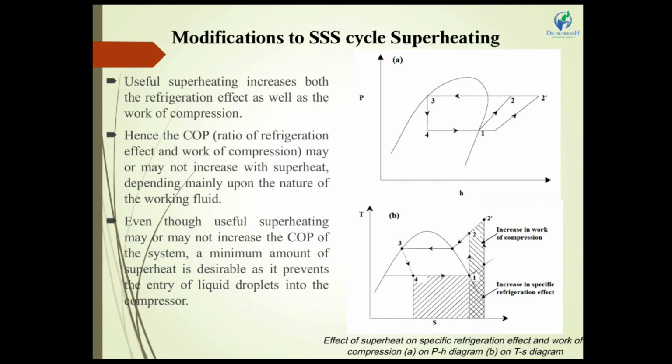The COP, the ratio of refrigeration effect and work of compression, the coefficient of performance, may or may not increase with superheating, depending mainly upon the nature of the working fluid. Even though useful superheating may or may not increase the COP of the system, a minimum amount of superheating is desirable as it prevents carrying liquid droplets into the compressor. In this diagram, we have to make that clear.